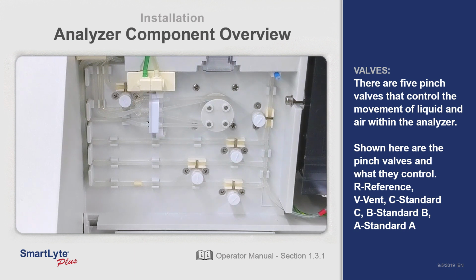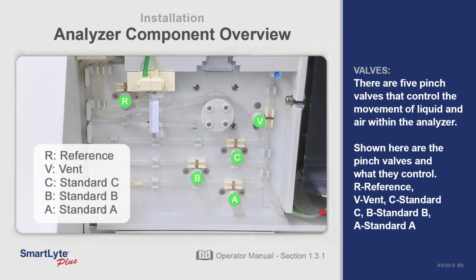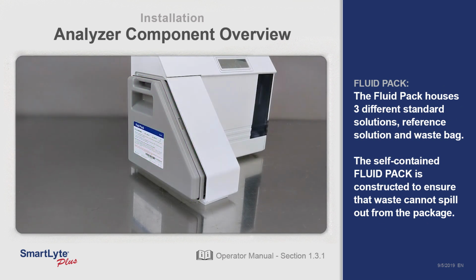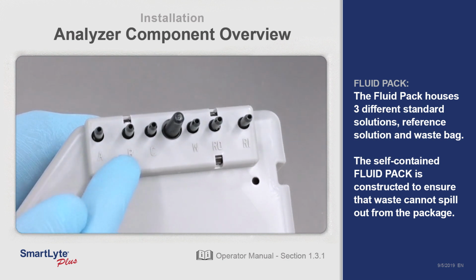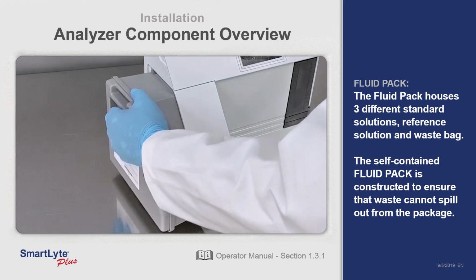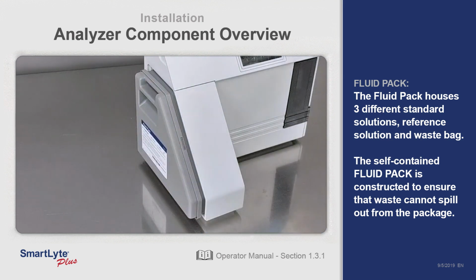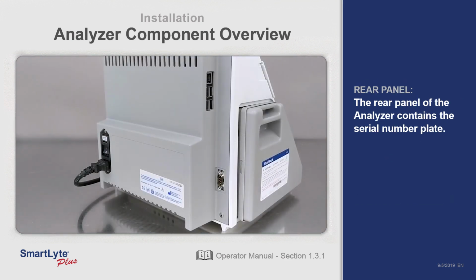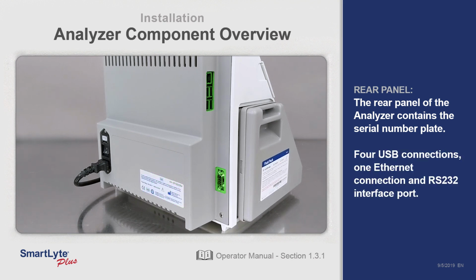Valves. There are 5 pinch valves that control the movement of liquid and air within the analyzer. Shown here are the pinch valves and what they control. Fluid pack. The fluid pack houses 3 different standard solutions, reference solution, and waste bag. The self-contained fluid pack is constructed to ensure that waste cannot spill out from the package. Rear panel. The rear panel of the unit contains the serial number plate, 4 USB connections, 1 Ethernet connection, an RS-232 interface port, and a power switch.